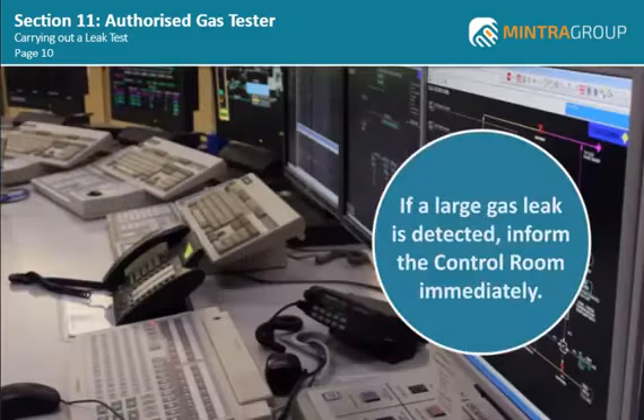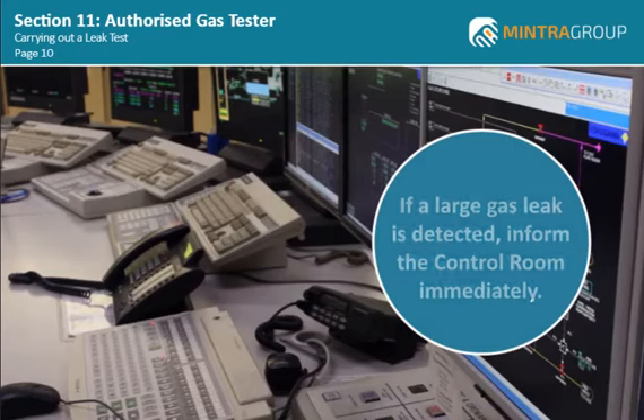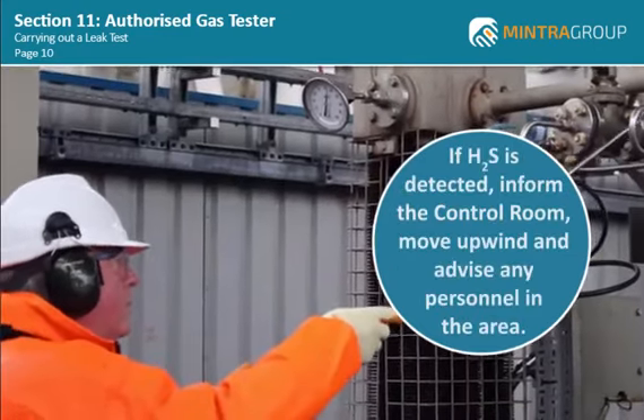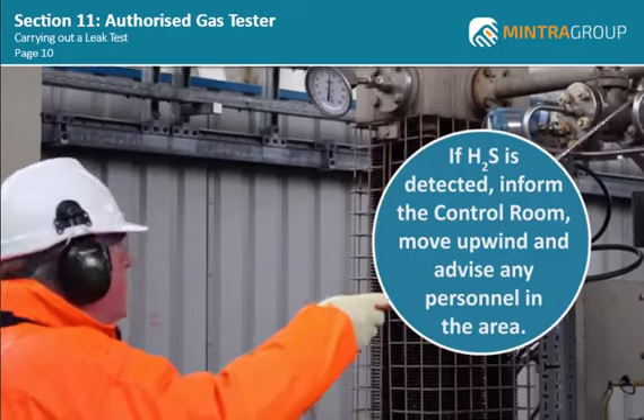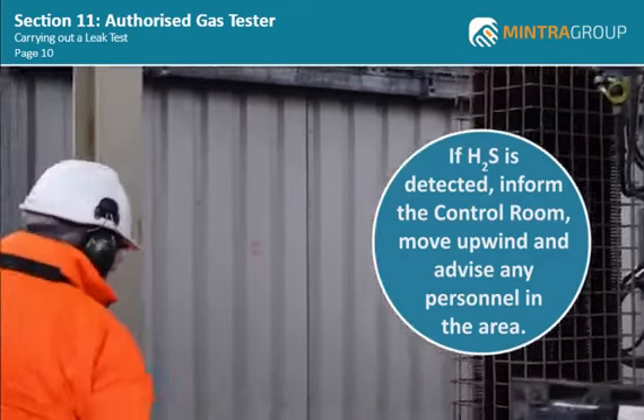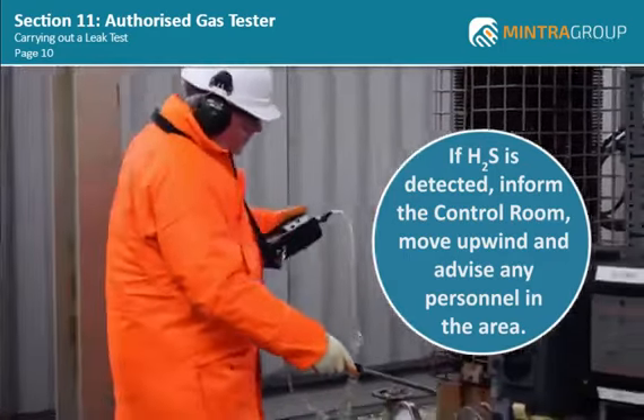If a large gas leak is detected, inform the control room immediately so that they can carry out emergency actions to isolate the system. If H2S is detected, inform the control room, move upwind from the leak, and advise any personnel in the area to do the same.